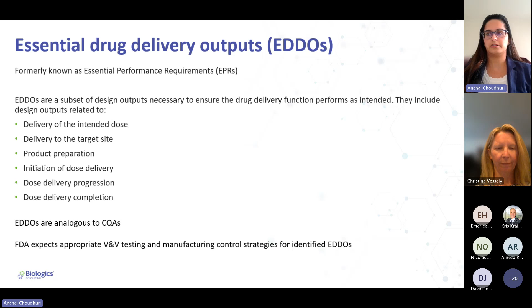Okay, thank you. So yeah, FDA does expect the V&V testing and manufacturing controls to be identified for these, what they are terming EDDOs, or essential design outputs. And just to clarify, V&V testing is not just needed for those essential outputs, but to address all design inputs and outputs. It's just that there's special focus given to EDDOs, where the testing is expected to be done in more worst case conditions. So preconditioning is expected. When you're testing these specific design outputs, they should already have undergone shipping and transport type testing, and testing should be done at end of life.